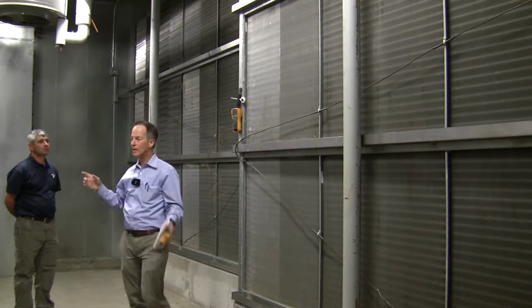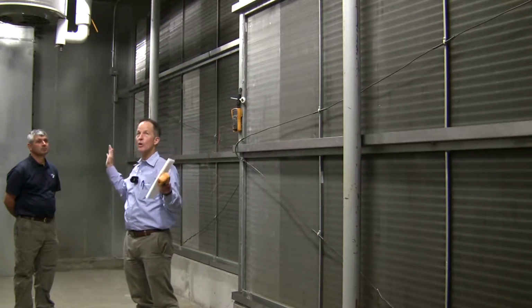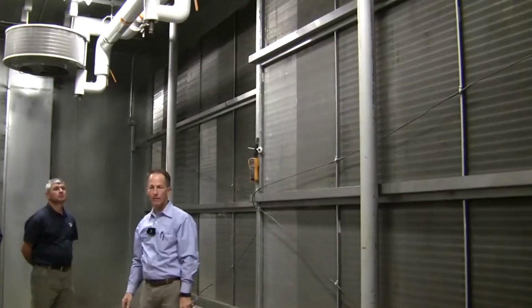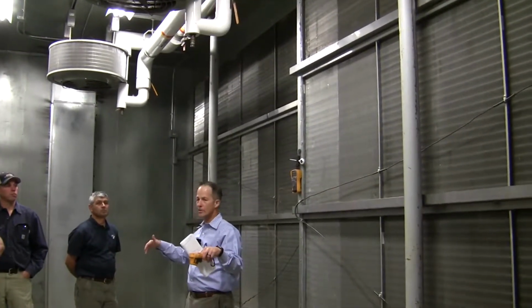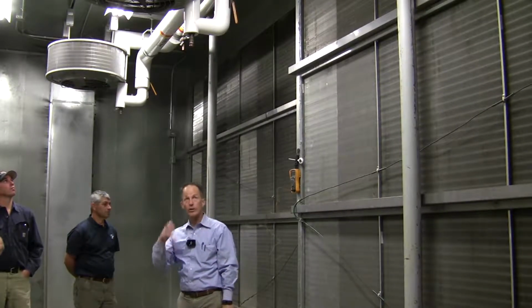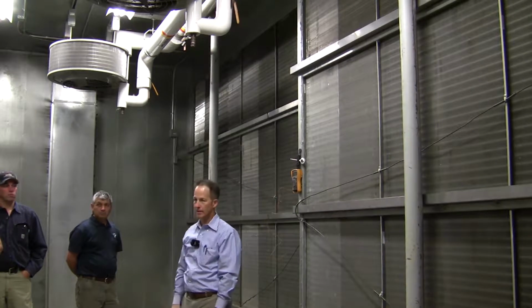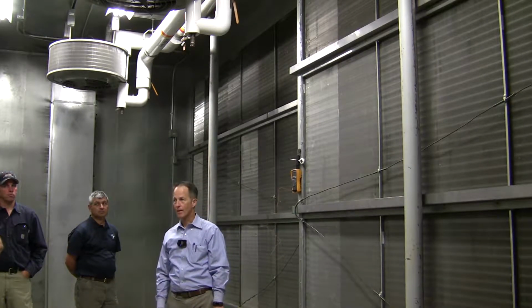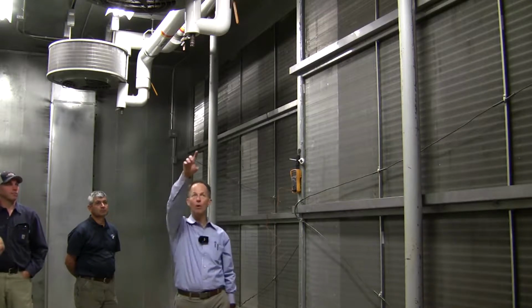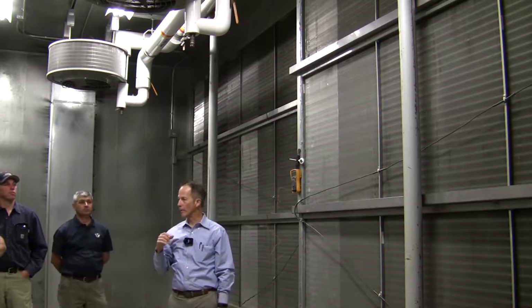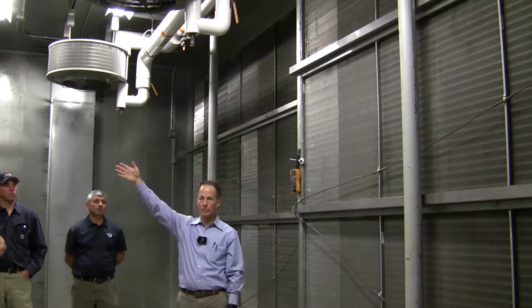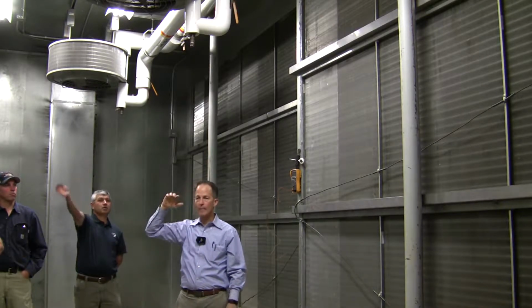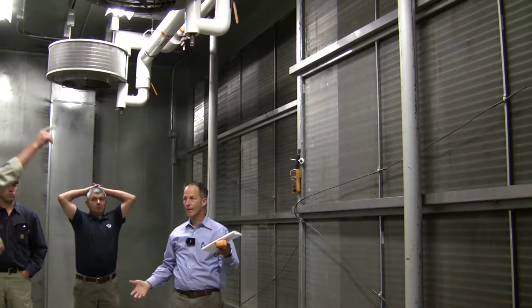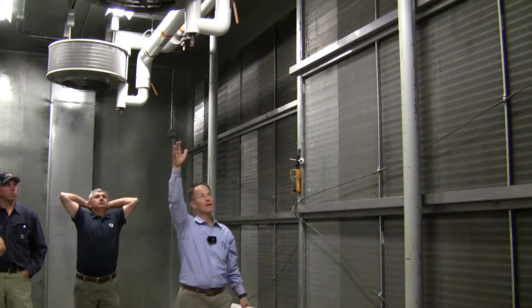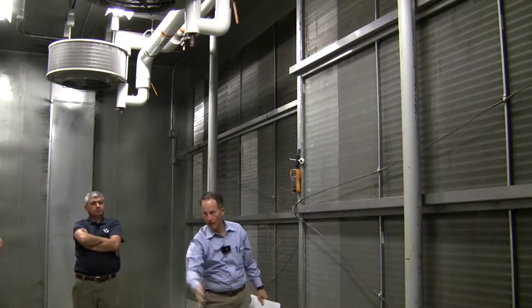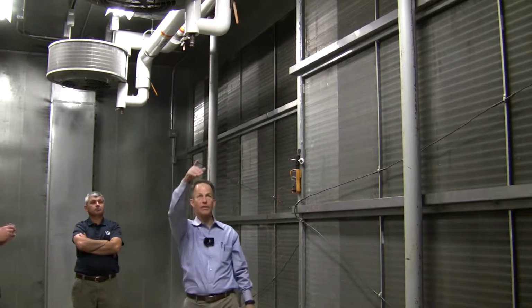And so in this case, this is a little bit of a weird one, right? We have these heaters up above that inject warm air into this area. What's going to happen if we turn these heaters on and we've got 30-degree air coming in? Not be 30-degree air anymore. Okay. What happens though with these fans? You got hot air coming off of them. Where's our cold air coming from? From behind us. What happens to hot and cold? Hot air is going through the top, the cold's going through the bottom. Yeah, so the hot air is going to stay pretty high, but the cold air is going to come down below because of the way that this is built.